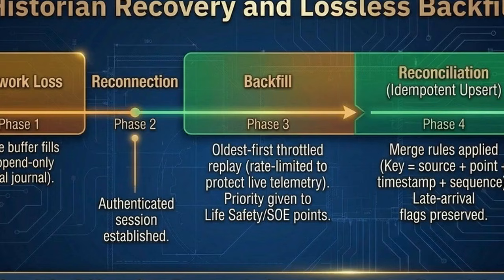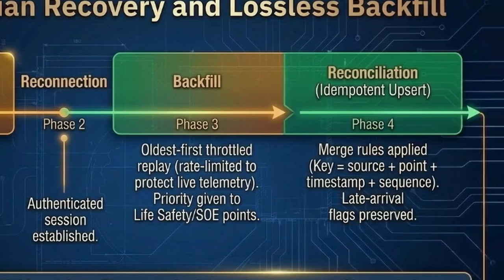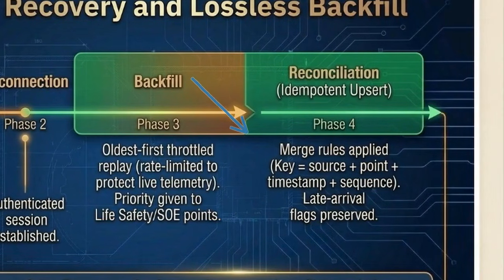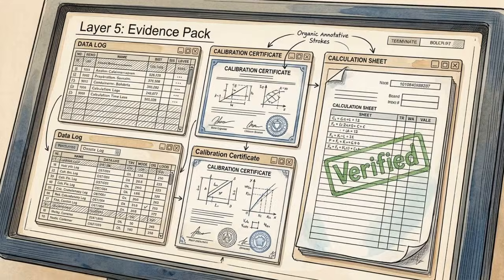This illustrates historian recovery. During network failure, the system triggers an oldest first throttled replay of buffered data, prioritizing life safety points. Phase 4 uses idempotent upserts with strict merge rules to fill historical gaps cleanly without creating duplicate accumulations. The data finally arrives at Layer 5, the evidence pack, where recovered field telemetry is translated into the mathematics of certification.